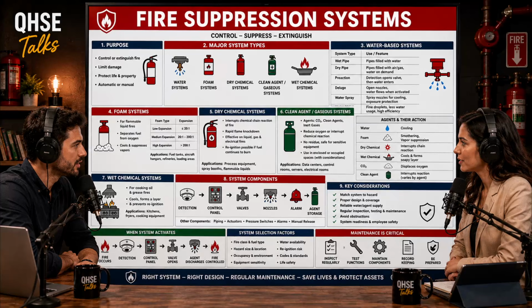Do they just pump it full of high-pressure air and see if it explodes? No. If the cylinder ruptures under air pressure, the rapid expansion of the compressed air creates a deadly explosion. That is why they use water, hence hydrostatic. Water is incompressible. So fill it with water, pump it past its normal operating pressure, and see if the metal stretches. Precisely. If the metal expands past its elastic limit and permanently deforms, or if it leaks, the cylinder fails and is destroyed.